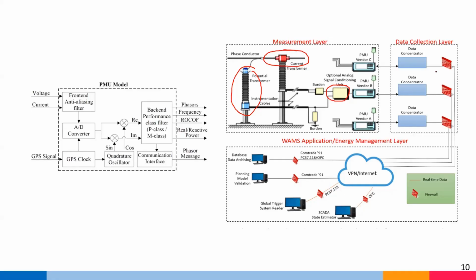So it will match which time stamp all the data corresponds to; for example at t equal to 0, whether data has been received from all places or not, and it will align that t equal to 0 data, because that information is embedded in the data itself, coming from a time synchronized device. So it aligns, for that particular instant, all the phasor information from all locations in the field. That is how we get the data at the control center.